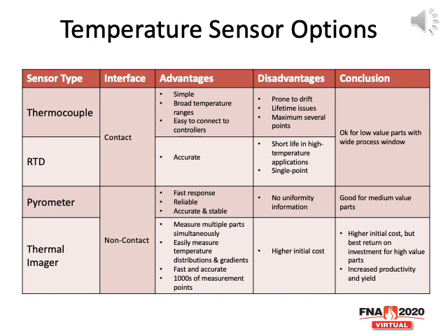measuring the workpiece. The pyrometers measure a single point on the workpiece, and you can put multiple pyrometers into a process if you want to get a gradient or see across multiple parts. But then the thermal imager, the big advantage there is it can see gradients within a part, and it also can measure multiple parts or multiple things within the furnace simultaneously.